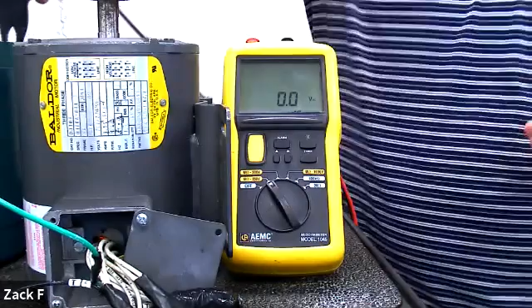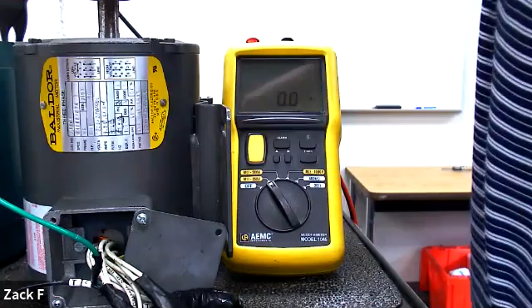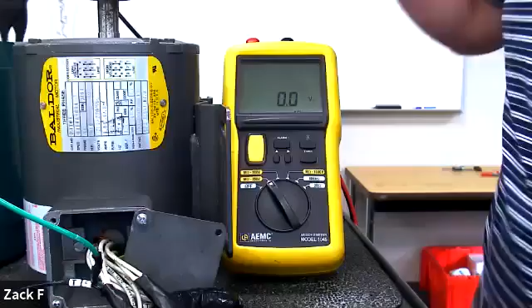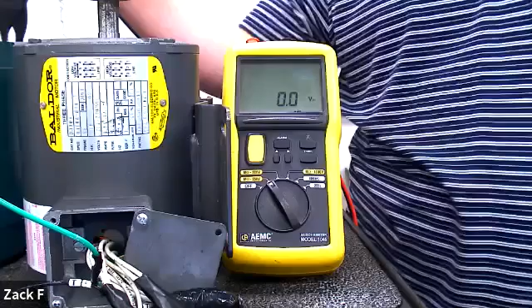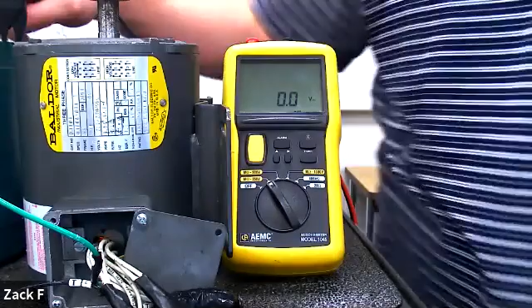I'm going to test this one and see what we get. This is T1. You want to make sure you have everything isolated. Some of these motors are sitting up on a block of wood, that's good. Some are sitting on the table, that's fine, as long as your leads aren't touching the table, otherwise you'll get bad readings. So I'm testing T1 to ground, holding the button down on the 250 volt scale.